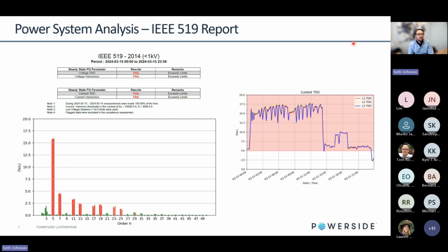But we also have the ability to look at IEEE 519, which is really the most common compliance standard for harmonics in North America. And this is a really important standard because pretty much all utilities in North America have a requirement that their customers have to meet this IEEE 519 compliance standard. However, not all of them do, or know that they aren't meeting these standards. And later on, I'm going to talk about a case study where it was really driven by a utility who found out that they were having a harmonics issue on their power distribution grid, and it really boiled down to a customer not meeting 519 compliance.